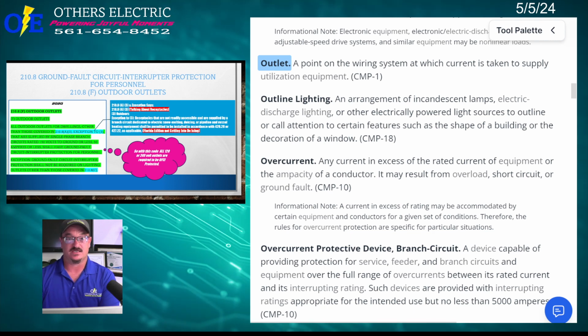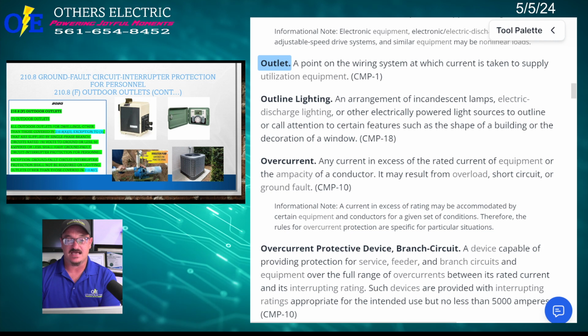All right, so now I know what you're thinking, right? These are all things that now have to be GFCI protected because they're 50 amps or less and are outdoor. Okay? Pool heater, if it's 50 amps or less, it's got to be GFI protected. You got a 120 volt circuit that's hardwired to your sprinkler timer, GFI protected. You got a 240 volt circuit that runs your irrigation pump, 240 volt or 120 volt, GFI protected. Condensing units, GFCI protected. That's new. That's big. But I want you to hold on there, because there's an exception.